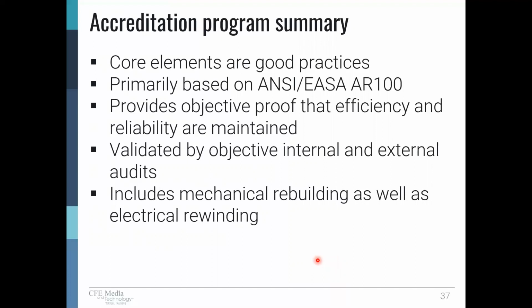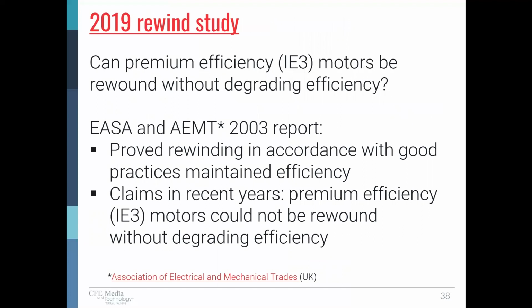Our big focus today has been rewinding, and we're going to move on from here into the rewind study that was done. But not every motor that comes into the service center for repair needs to be rewound. So those motors that come in with bearing failures or maybe a bent shaft and so forth, we're going to follow the same good practices all the way through the testing of the windings, even if they're not being rewound. We're going to do whatever tests we can to affirm the integrity of that winding, so that the motor goes back in and maintains its efficiency and its reliability.